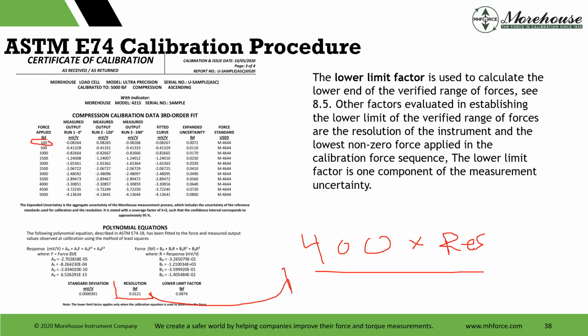So any customer, theoretically, 400 times the resolution is the first force point we could calibrate. And then the other thought of this equation is 400 times the lower limit factor is going to be the first point in the verified range of forces, which we'll cover that later. In this example, the customer, if we would have taken a low enough force point, they could have driven this cell down to about 32, 33 pounds. So since we started at 100, guess what? The Class A verified range of forces has to start at 100.